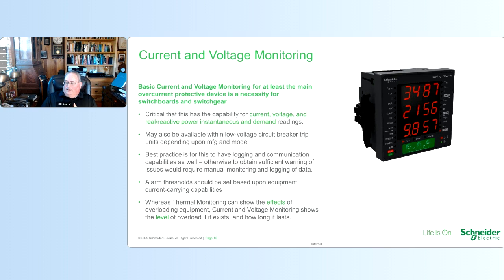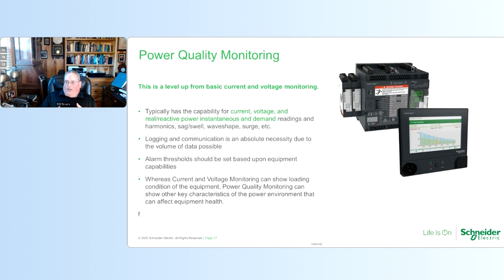Alarm thresholds for this type of metering should be set based upon the current carrying capabilities of the equipment. Unlike thermal monitoring, the basic current and voltage monitoring shows loading issues that are one type of causative factor for equipment insulation overheating. Expanding monitoring to include power quality monitoring is a step up, and it allows for the addition of harmonics, sag, swell, surge, wave shape, and other data to give a more complete picture of the power environment that the equipment is being exposed to. Logging and communication capabilities are even more essential than for basic current and voltage monitoring, just due to the sheer amount of data available and the optimal time frame for reacting to power quality events to avoid long-term damage to the equipment.